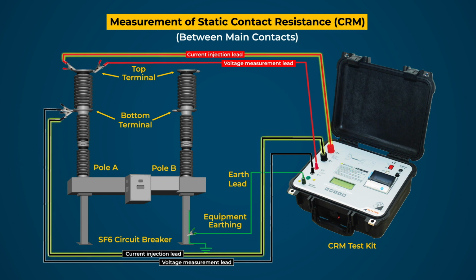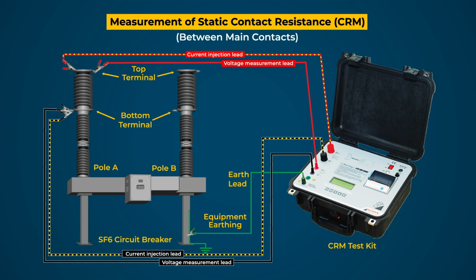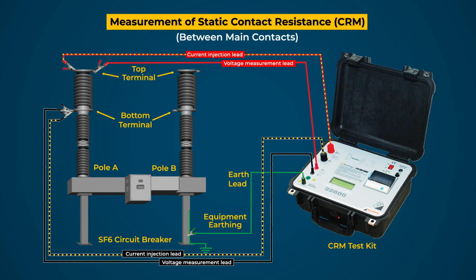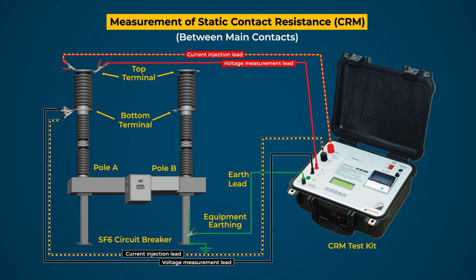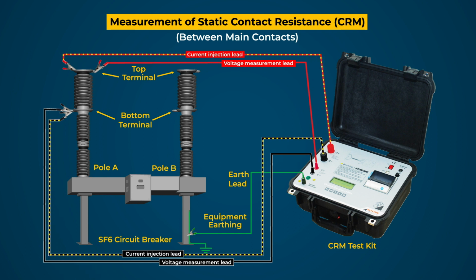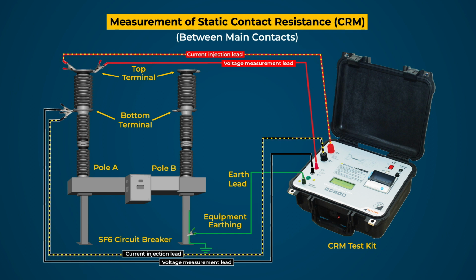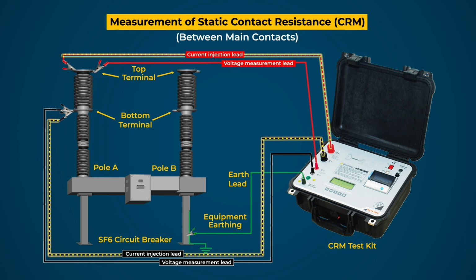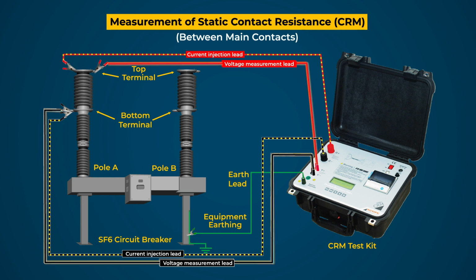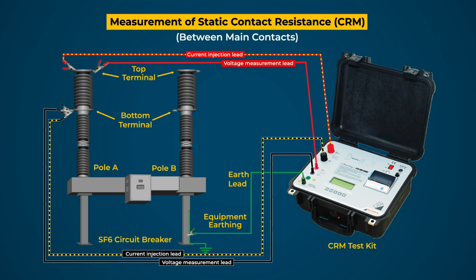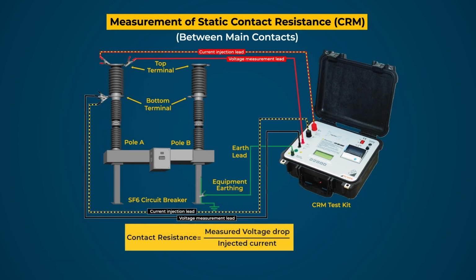By this, a DC current is injected through the main contacts of the breaker under test. And due to the contact resistance between both contacts, a voltage drop is observed between them. Finally, the test kit measures the injected current through the main contacts and the voltage drop between the main contacts, and calculates the contact resistance by the ratio of measured voltage drop and injected current.